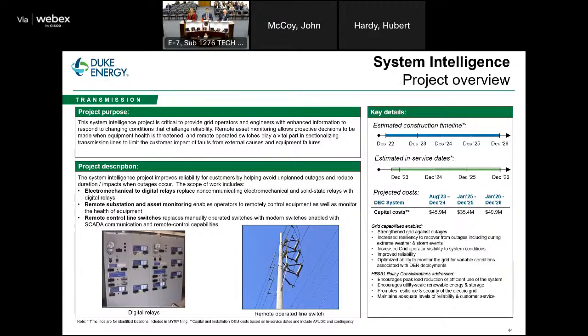So these new relays, they perform that function, but they also provide specific information to the operators on where that problem occurred. And they do that through analyzing fault current and determining distance to faults. So what we're doing is we're upgrading the information that the grid operators have so they can make intelligent decisions on how to reroute power. And they do that through circuit breakers and substations, and then remote operated sectionalizing switches that we deploy out on transmission lines. And the advantage of this is we can break up transmission lines that are 20, 30 miles long, sometimes with multiple different fingers or radials or taps emanating from them. We can break that into smaller segments.